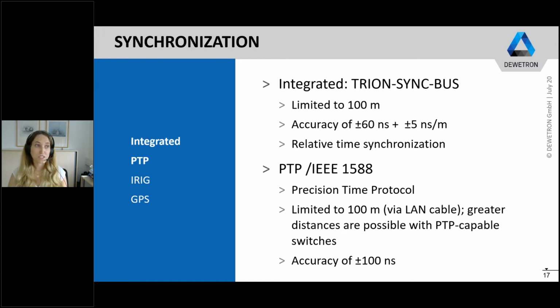So there are different possibilities of synchronization, which also depends on where the measurement systems are located and which accuracy is needed. For an integrated possibility, I would like to mention our own integrated synchronization source, which is the TRION-SYNC-BUS. This is always included in our DEWETRON systems. It has a relative time synchronization accuracy of 60 nanoseconds plus minus 5 nanoseconds per meter, and is limited to 100 meters. It is a very easy synchronization possibility.